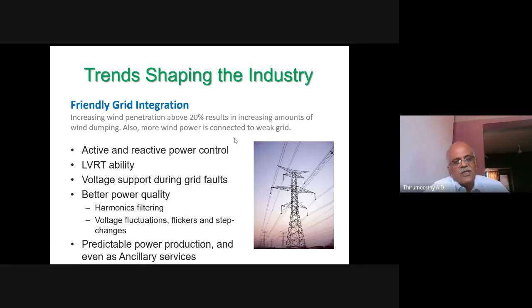But for your information, I can tell you that all the solar generators, solar inverters, even the windmill fully convertible machines can supply reactive power when there is no generation also, especially the solar generators. That phenomenon is called Q at night. The inverters can be made operative during the night when there is no generation and supply only reactive power to the grid whenever they require, when they ask for. So that is a kind of ancillary service to be operative from the renewable energy sources in tomorrow's scenario.